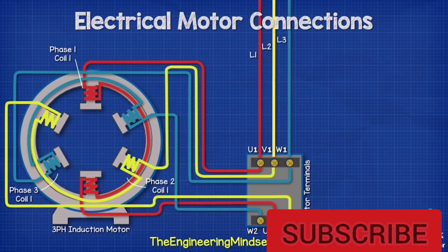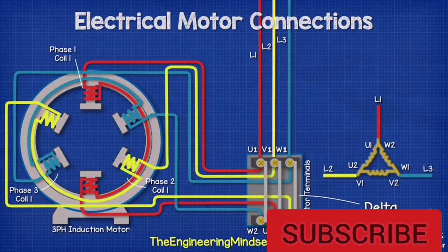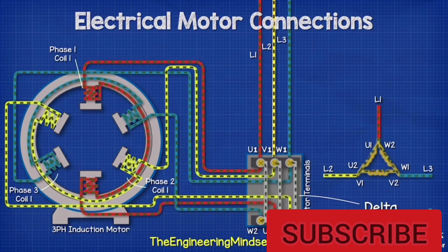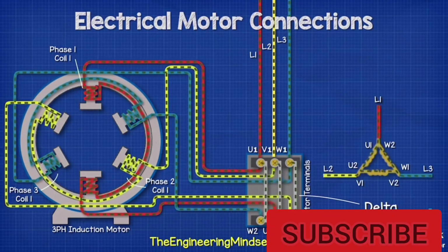We now bring in our 3-phase power supply and connect these to their respective terminals. For the motor to run, we need to complete the circuit, and there are 2 ways to do this. The first way is the delta configuration. For this, we connect across the terminals U1 to W2, V1 to U2, and W1 to V2. This will give us our delta configuration.